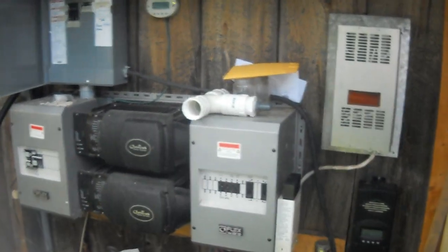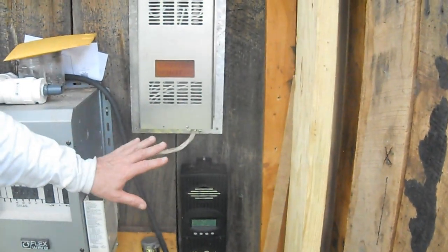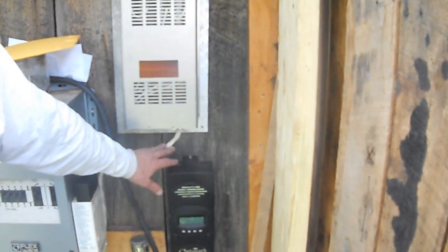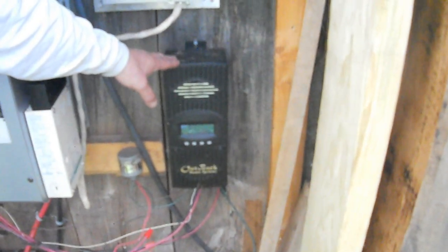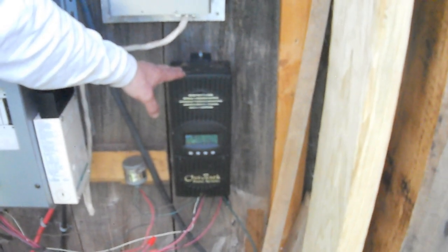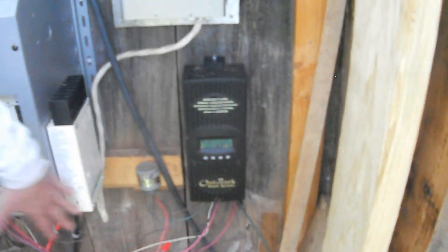The other part of the system is the solar panels coming in. Since they have variable voltage and variable input, that required a whole separate control system. But it feeds into the same setup, which accepts voltage anywhere from about 40 to 150 volts, with the output set at 48 volts, so it automatically regulates.